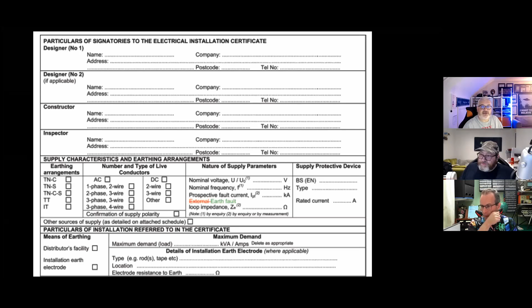On the next part of the certificate, the bottom part, whole new section - they've deleted extraneous conductive parts, then put if RCD main switch, they want the type now, which is a great insert. But this new schedule of inspections, the outcome positive on 1, 2, 3 - condition of consumer's intake, parallel switch to alternative source supply, methods of protection, basic protection. This is a whole new section now in the electrical installation certificate, kind of a throwback - remember when they used to have that little tick list you had to comply with? This is kind of a modern version of it, I suppose. At the bottom they've deleted 'attached schedules as part of this document' and changed it to 'this certificate is valid only when schedule of test results are attached'.